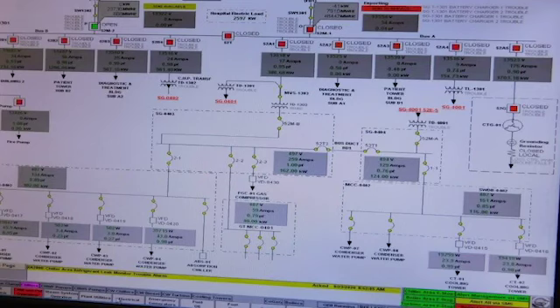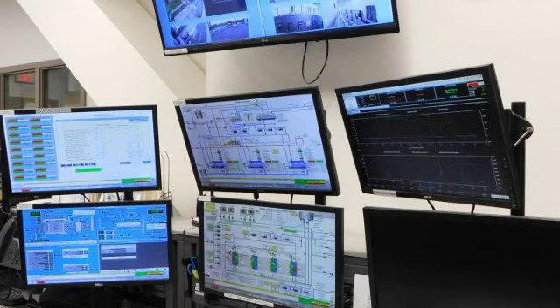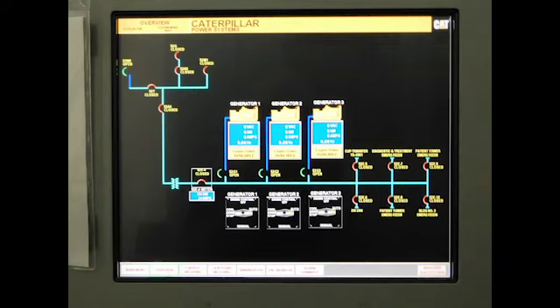We'll switch over here to the electrical HMI. The entire facility is controlled from a central control room, and we have full status of the entire electric system from one central spot. And then we can drill into the CAT ISO control system, which manages the diesel generators themselves and allows us to conduct testing. And we test right on the grid. We don't need a load bank.